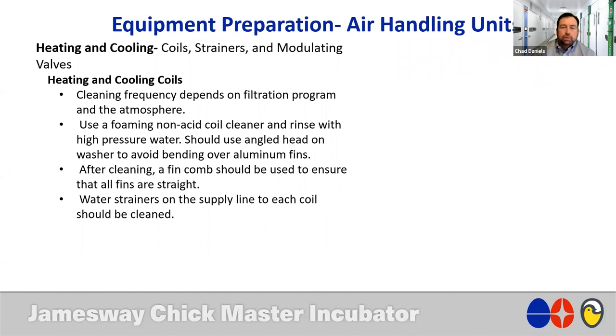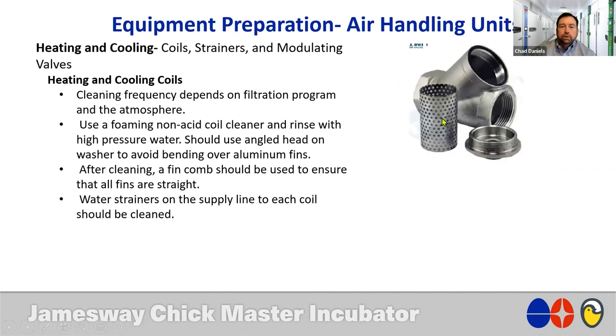What's different with having chilled water and hot water flow through coils is that generally on those coils, you're going to have a water strainer, and it's generally going to be a Y strainer, like this image here that I'm showing. If you pull this cap off of this Y strainer, you'll see a screen of some sort that slides right into that chamber. And so all the water that enters that coil, whether it be chilled water or hot water, has to go through a screen or a strainer. And so a seasonal change is a very strong reminder that these strainers should be removed and thoroughly cleaned to make sure that we don't restrict water flow.